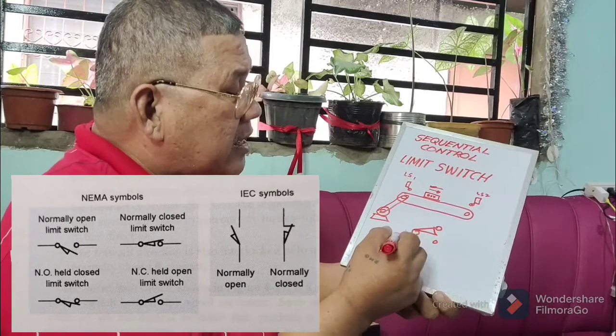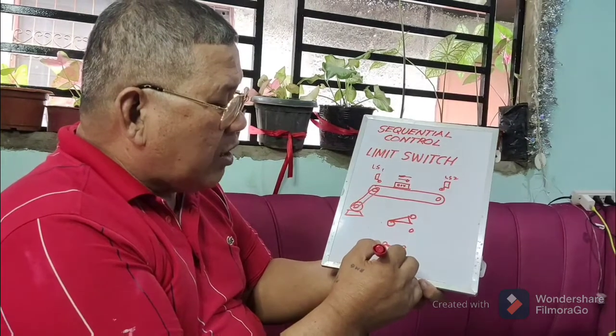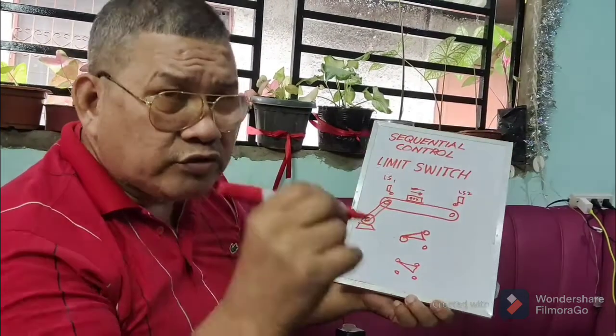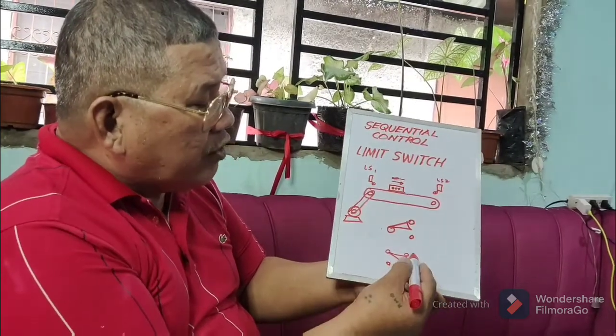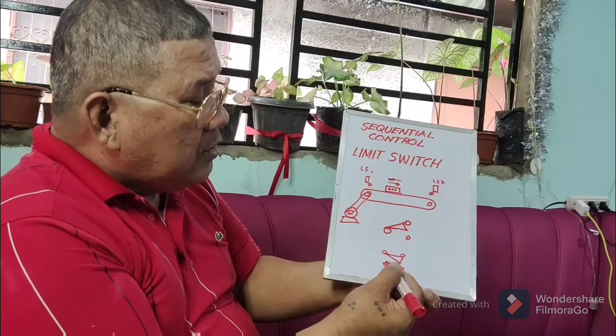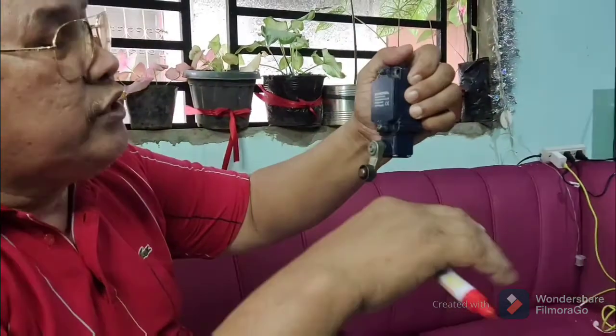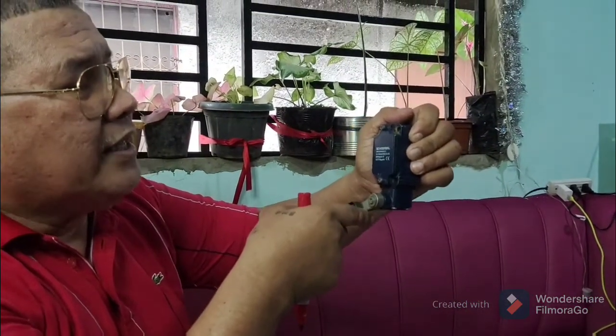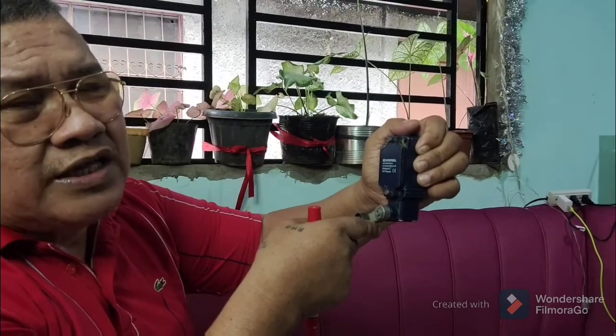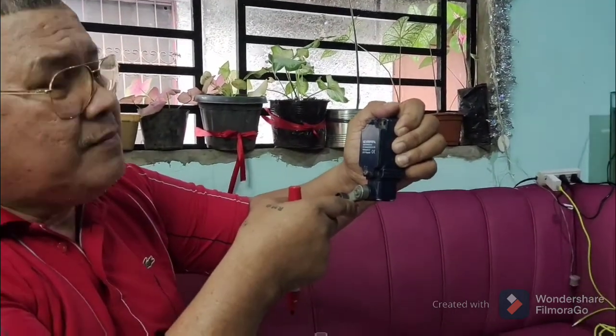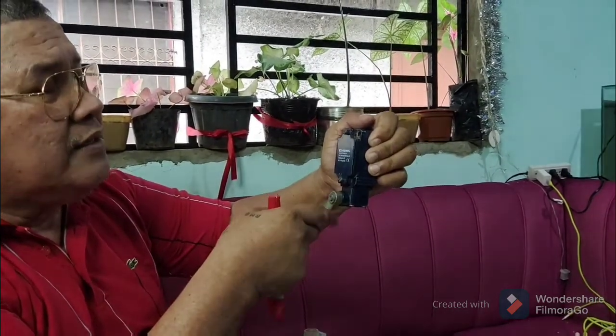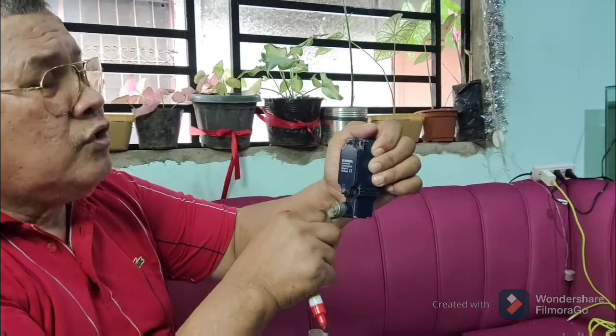So we have the symbol of the limit switch. This is a three-terminal contact, and we also have a four-terminal contact. Later I will let you see the inside of the limit switch. You have normally closed and you have normally open. When this lever is pushed by an object hitting it, the normally open will close and the normally closed will open.